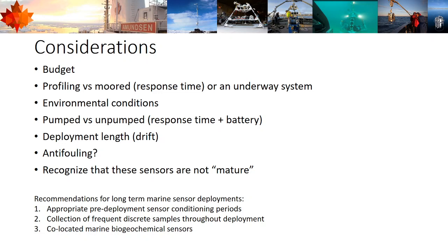Pumped versus unpumped. So this is something to consider. If your system is unpumped, response time is usually faster and battery consumption is quite a bit less. If your sensor system is pumped and it's moving water through the system actively, that takes power and it slows the measurement down.